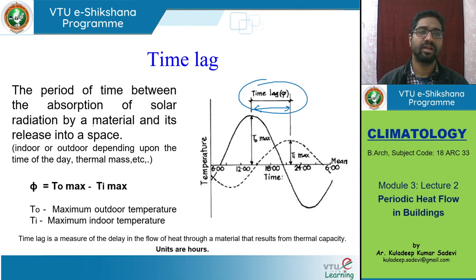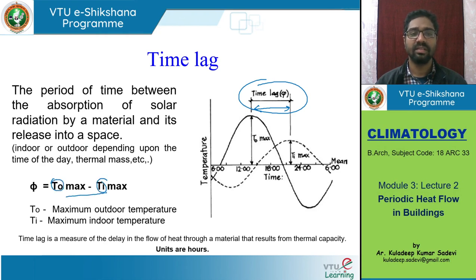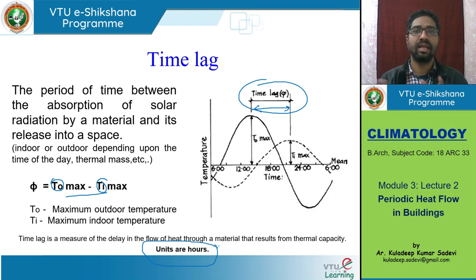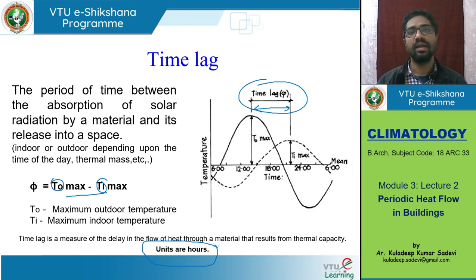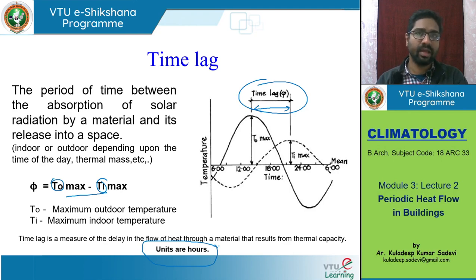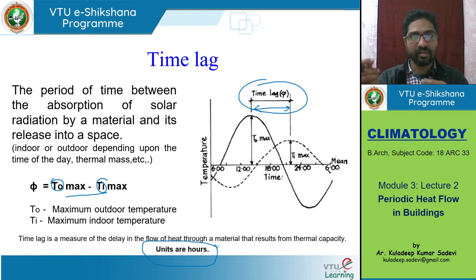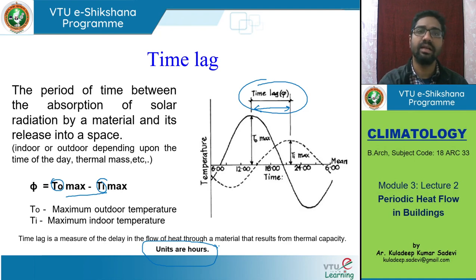Time lag is the period of time between the absorption of solar radiation by the material and its release into the space. The difference between the time of outdoor maximum and indoor maximum is what we calculate as time lag, measured in number of hours. For example, the time lag for a given wall might be six or seven hours. Time lag is not just a characteristic of a wall material alone — a nine-inch brick wall facing east may have a different time lag than the same nine-inch brick wall facing another direction, because of the varying rate of temperature rise and the time it takes for those temperatures to propagate indoors.